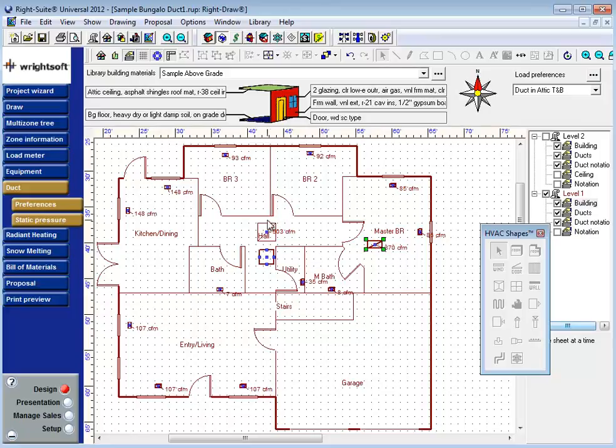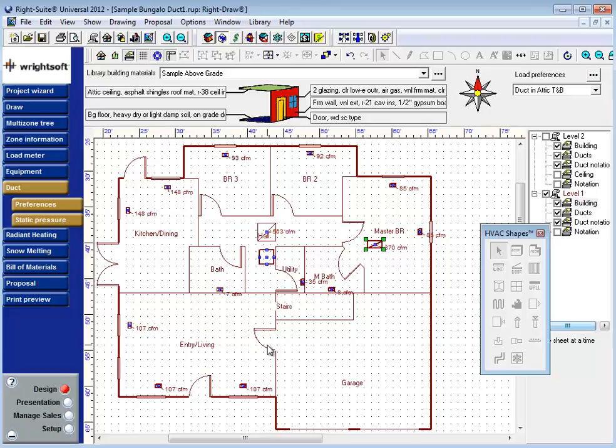Now, this may not be what you're looking for. For example, this return grill here in my master suite should only be pulling back air from the master suite, these three grills here. The fact that it's pulling back air from the utility room and some of the entry and living room is going to be a problem.